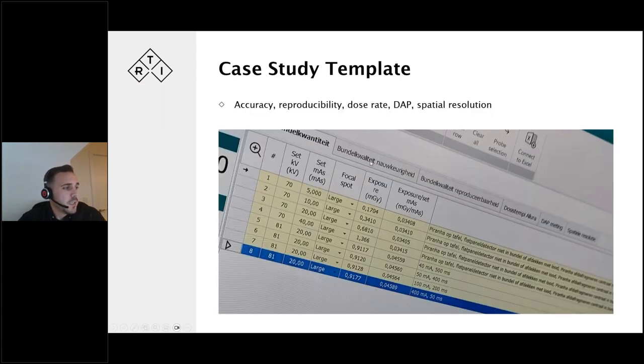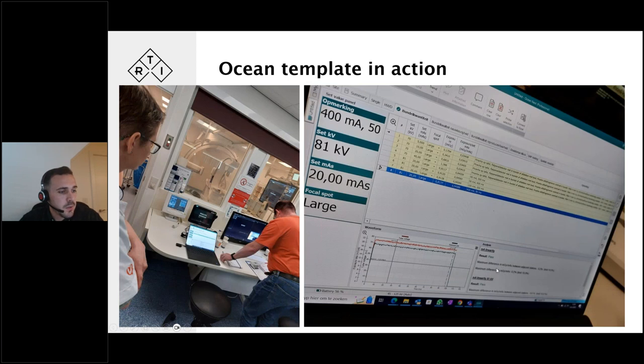Here you can see it says a different language - it's Dutch, so I've translated that for us here. In this multi-page template we see accuracy tests, reproducibility tests, dose rate tests, DAP tests, just like I showed. The engineers, for example, have to set different mAs settings - 5, 10, 20, 40. They get an exposure value, but then what they need to do according to their national regulations is calculate exposure relative to set mAs, and you can see here 0.034, 0.034, 0.034 all across the board. Down here, maybe a bit difficult to tell, but their pass criteria was 0.2%, so the whole thing passed.